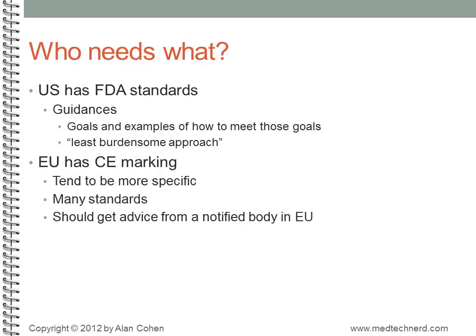The CE mark is awarded by organizations known as notified bodies, which are accredited by governments. There are dozens of notified bodies, both publicly and privately run, and they all charge fees for their services. In general, a device maker should select the notified body they'll be working with early in the development process, come to an agreement around which standards must be met, and continue to work with them through the development process to ensure that they're on the right track for gaining approval once they're ready to go to market.